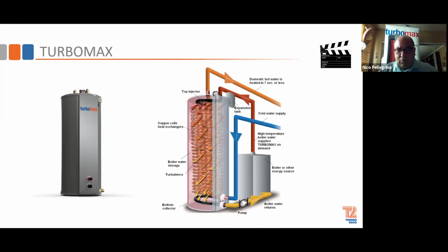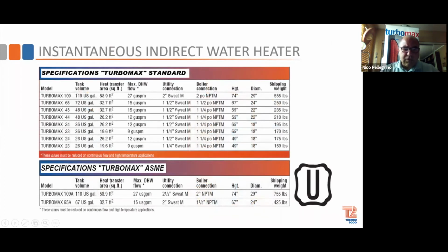So it's a little bit different thinking. If you look at the models, the first number of the model is how many US gallons are in the tank of boiler water. The second number is how many coils are in the Turbomax. And then this is your domestic flow, the maximum flow that you can get out of each Turbomax with the amount of coils that are in there. Each coil represents 3 gallons of flow. Now, there's a lot of guys that are going to say, we do make the 109 and the 65 in ASME if some engineers are speccing it or want to spec it.